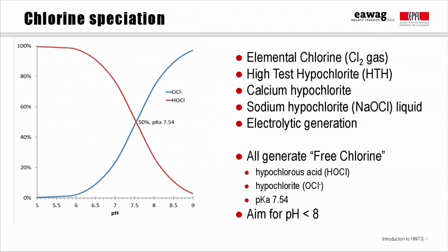When we talk about chlorine, we can refer to many different things. Large drinking water utilities typically use elemental chlorine, present as chlorine gas, which is cost-effective and includes, by definition, 100% chlorine. The next most concentrated form, also used in many utilities, is high-test hypochlorite, or HTH, which contains about 60 to 70% chlorine and comes in powders or tablets.